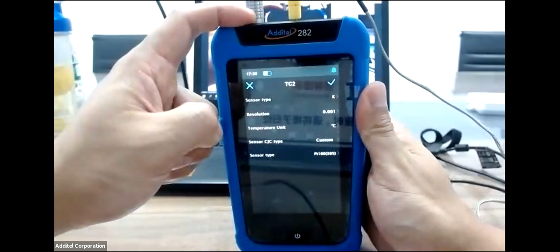When you select custom, that means you're going to use the other channel of the 282 as a cold junction compensation sensor. For example, we have channel 2 as a thermocouple Type K. If we select custom cold junction type, that means we're going to use the channel 1 sensor as a CJC sensor, so we can select a PT100, PT50 or something.